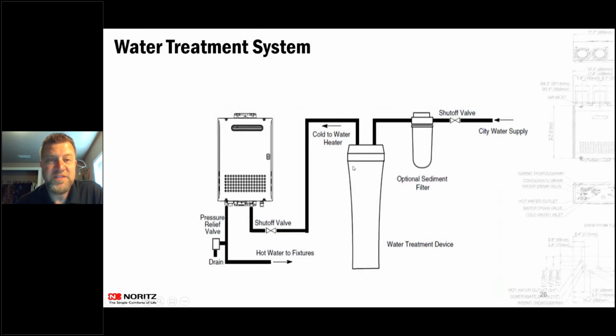So the best thing for any house, especially here in Utah, is water softeners. They are great for tankless water heaters, for any water heater actually. But you can use those small tripolyphosphate filters, Siliphos, anything that's physically treating the water in some way, whether it's coating those minerals or removing those minerals, is great for tankless. It's going to let those units run. Like one of our EZ units has a 25-year warranty. As long as you're treating that water and flushing it, it's going to last 25 to 30 years.